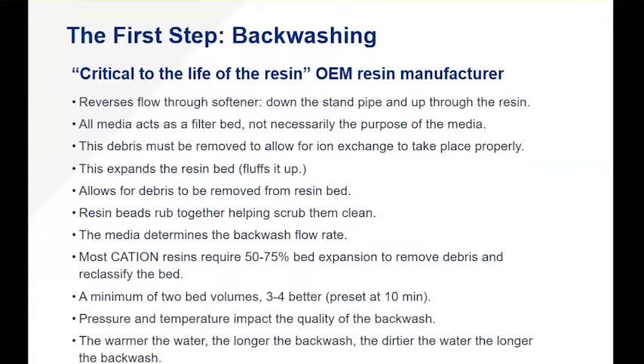In this process, what we are doing is removing the bulk dirt off the unit. Because every media — every packed column you have, and that's all a resin tank is — is a packed column of beads. Whether that is resin, sand, activated carbon, whatever media you put in there, it acts as a crude filter. It's going to load up with dirt. And if there's any non-polar material in there, it's going to attract organics to stick to it, and that's going to happen in the upper third of the bed.